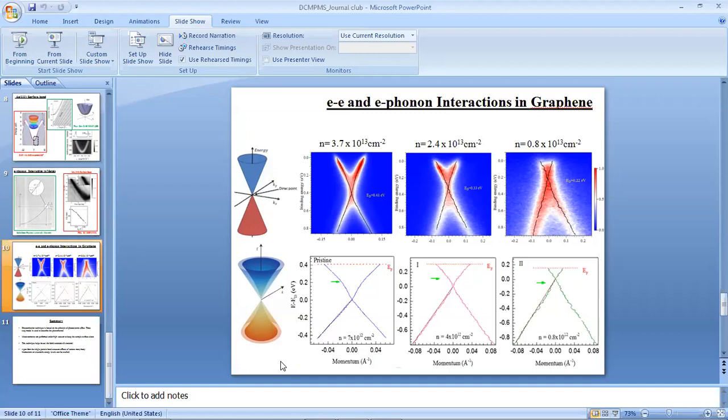If you make it very small, fewer electrons will go inside the electron analyzer, and the experimental time will also increase. So we have to make a trade-off between these two things. We keep it finite, maybe 0.3 mm of slit width, around that much.